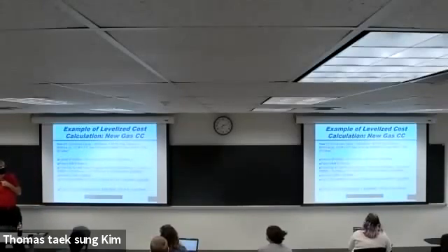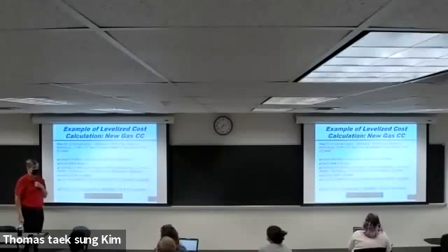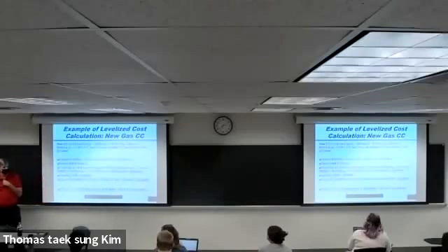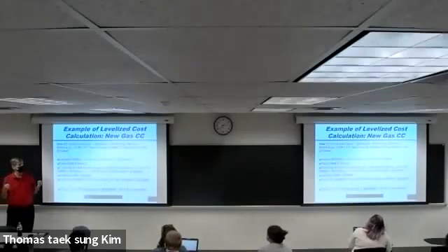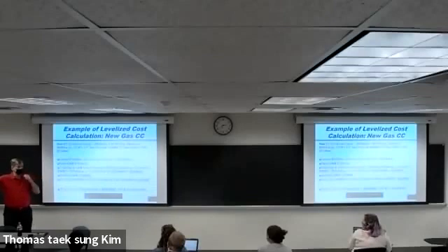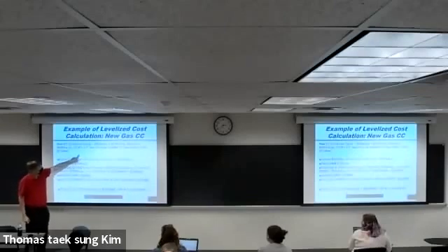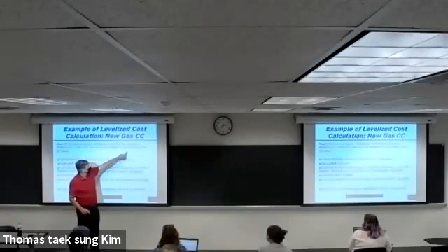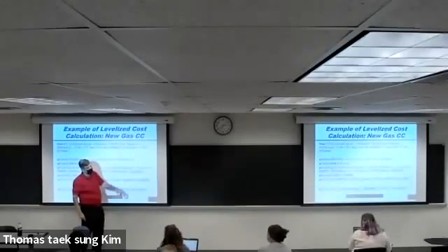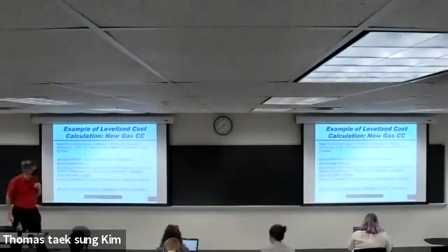7,000 BTUs per kilowatt hour is really close to 50% efficiency. And we said 3412 BTUs in a kilowatt hour. If you did 100% efficiency, you could convert every bit of the heat energy that came out of burning fuel into kilowatt hours, which you can't. If you could, it would be 3412. Well, 6824 would be 50%, so this is a little less efficient than 50%.